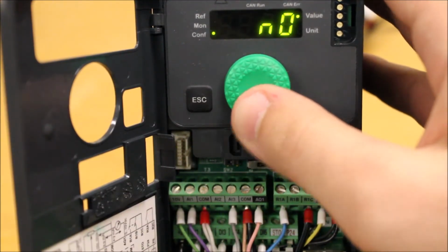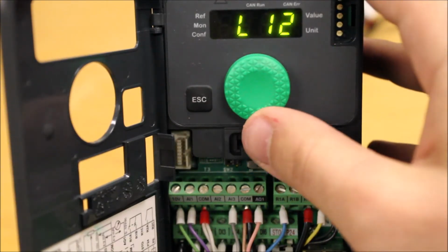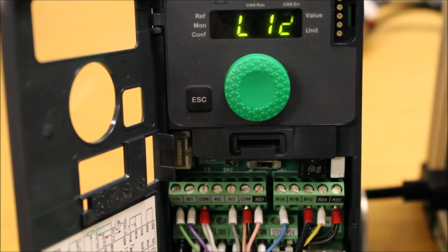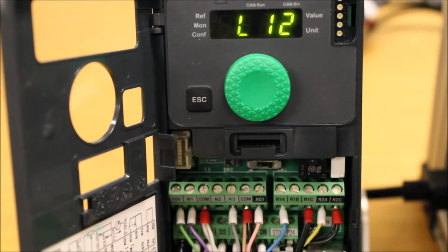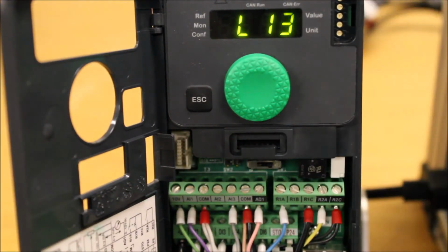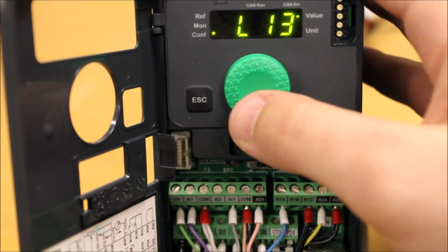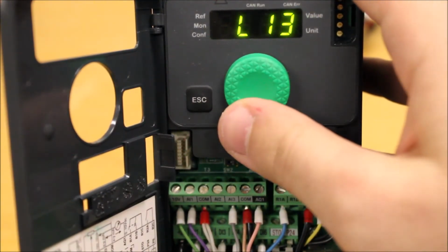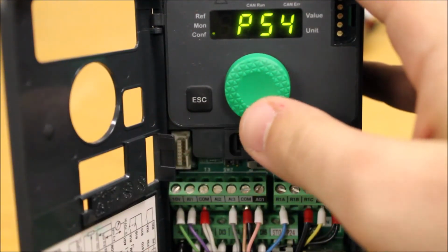Okay? And if you enter on PS2, it says no assignment right now, but you can change it to whatever logic input you want. The most common ones are like logic input 3 or 4 or 2 as an example, only because LI1 is normally, or DI1 is normally a run forward, so there might already be predefined inputs on certain logic inputs. But for our purposes here, we're going to go ahead and program LI3 or DI3, which is the same thing as LI3 by the way, as your first preset. So you just want to enter on that.